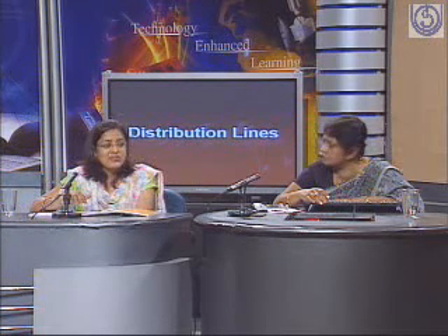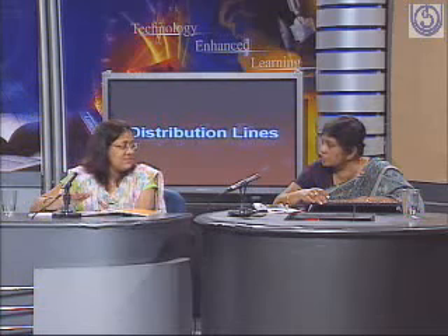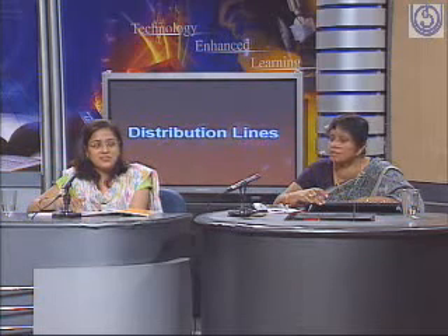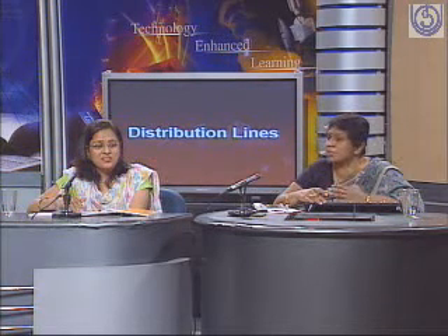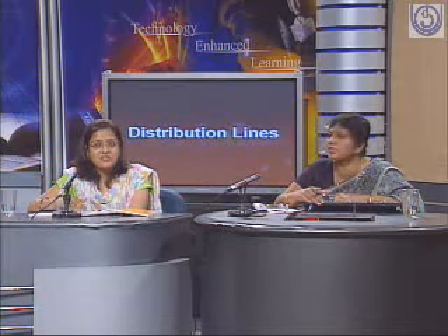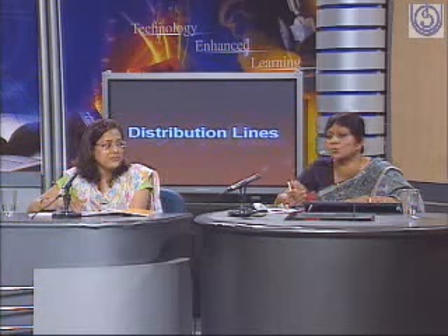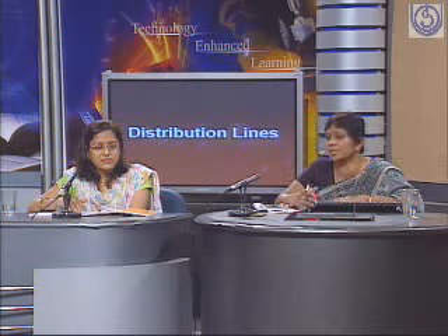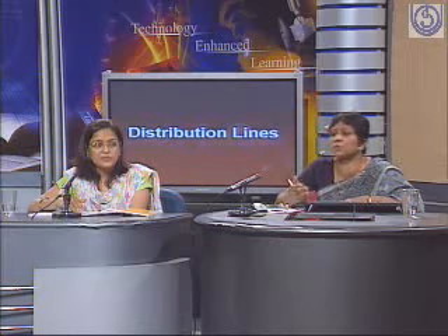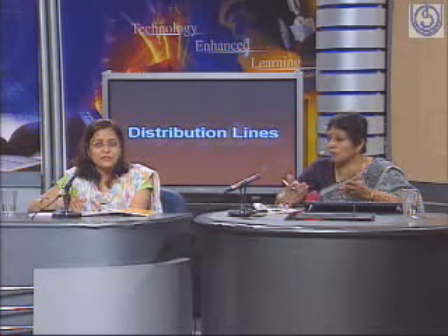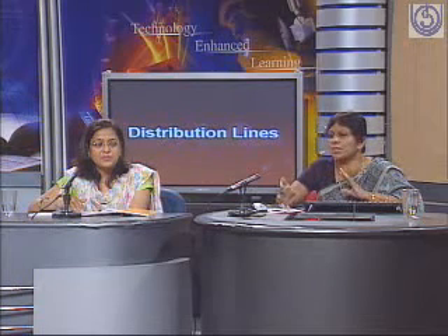He's asking why we are taking only 11 kV, 22 kV, these figures. These are the voltages which have been chosen by our country. In other countries, they do have 6.6 kV also. You can choose any set of voltages, but once you choose a set of voltages, your entire system is designed for that voltage. For example, in a disc insulator, we have taken 11 kV and we put 3 discs for 33 kV. So you have to choose some voltage, and the equipment is designed for that voltage.